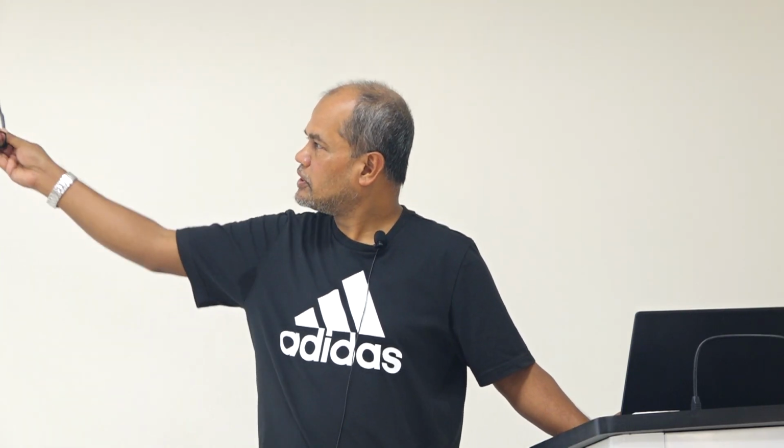So again, I do have a few slides, but you can read about resonance instability. That mainly happens due to subsynchronous resonance, like the resonance, right? XL equal to XC, right? So that resonance could be between the compensation and the electrical behavior of the generator, and sometimes we have mechanical resonance as well, between the mechanical torsional frequency and the turbine generator shaft. So mainly here, when you have an offshore wind farm connected to the transmission grid, you might have that problem.